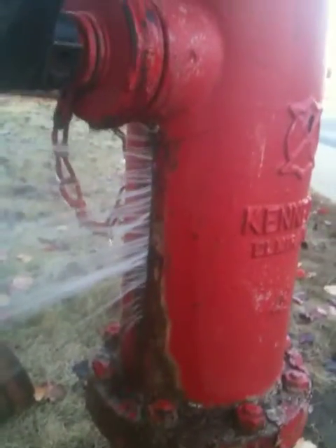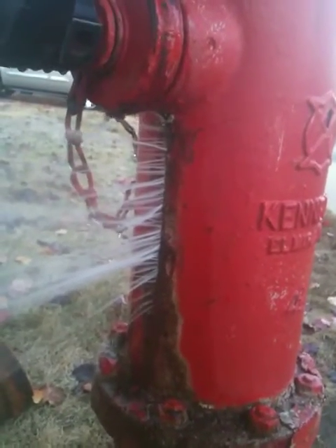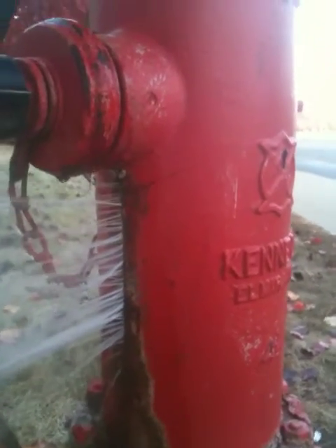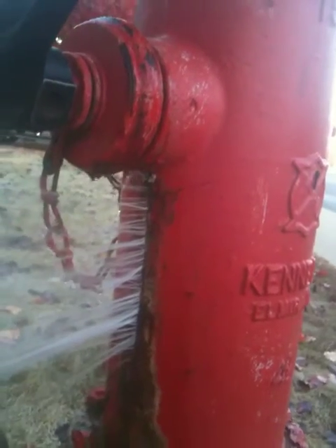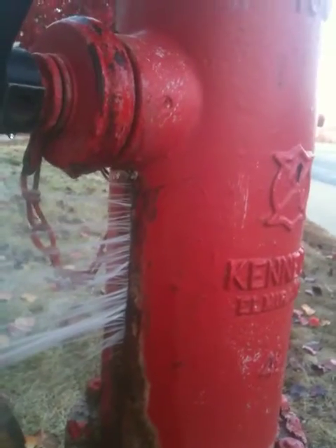November 18, 2010. Commercial location. Got a hydrant that is completely split right up, vertically up the barrel. This hydrant was found predominantly in the off position — the auxiliary valve was completely off on it. And when I went to turn the auxiliary valve on, this is what happened: water started spraying.